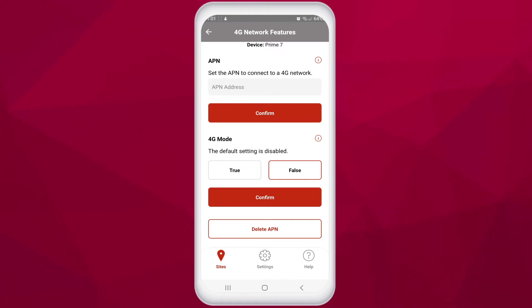Below this you have 4G mode. You can choose whether your unit connects to a 4G network via this feature. Choosing false will mean that the unit will not try to connect to a 4G network and will use only 2G and 3G connections. This can be preferred by users who use a pay-as-you-go SIM as they may not have 4G compatibility. However, 3G networks are being closed down by carriers globally — it has already started in the USA and the UK is scheduled to follow soon. We recommend a 4G connection to make the best connection possible for the unit to work as intended.